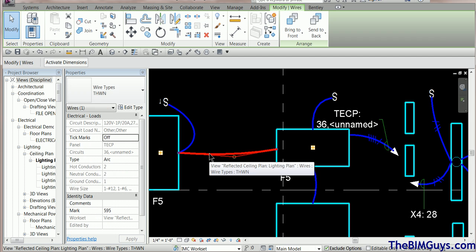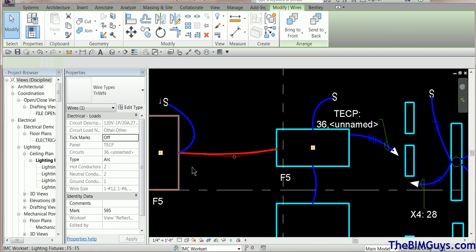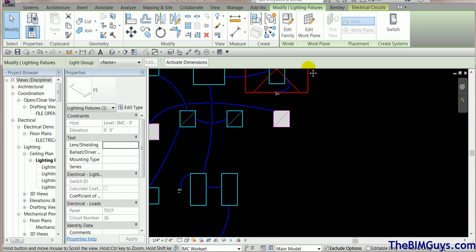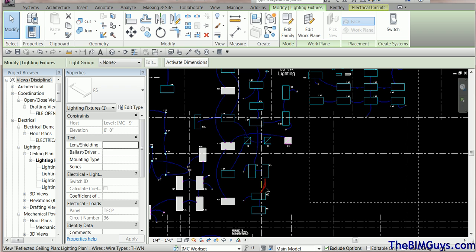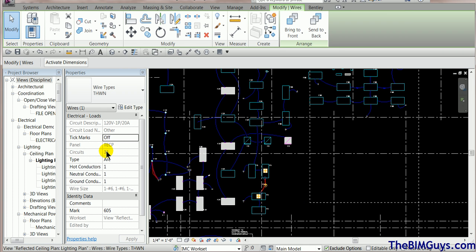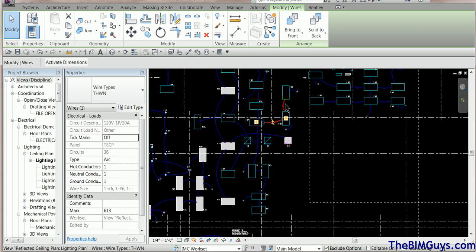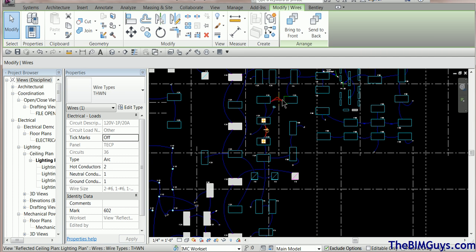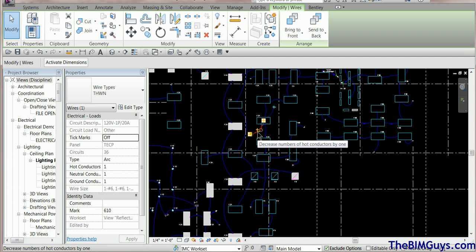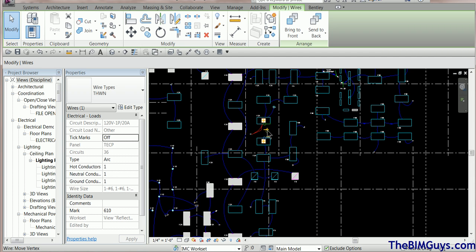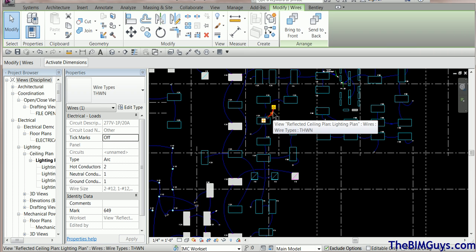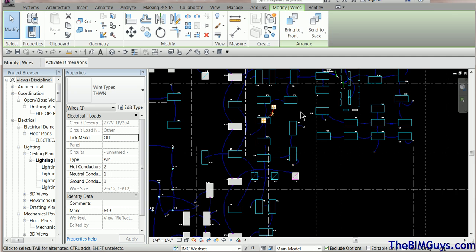When I pick on the wire, it says '36 unnamed.' I try to track it back — all the way to the end it reads C-Circuits 36, which looks fine. But at some point along the way, it picks up an unknown unnamed circuit. Walking back through the wiring, everything looks pretty good until we pick up something weird somewhere around here. It's not exactly clear where the unnamed circuit is being picked up, but we can spot a small unnamed piece right there.